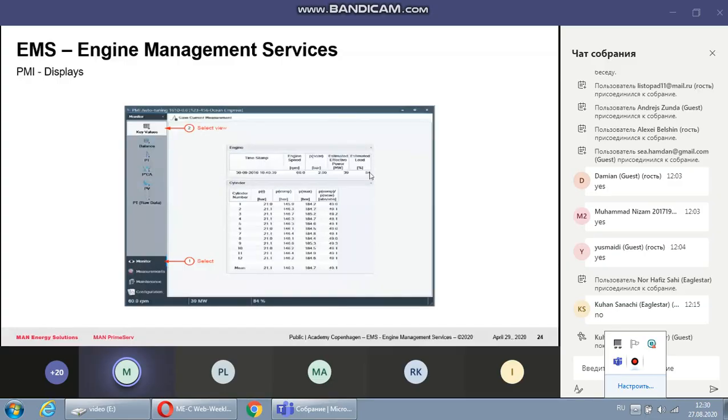So you took +5. Then waited for some time, 20-30 minutes, and you found the difference is 75 to 84. So now you go manually to the FQS, click, and then with the arrow mark showing downward or upward, push and see whether 75 becomes 80 or 75 goes to 72. So if you are not sure which direction you need to go, just increase by 2 or decrease by 2 and watch what happens. Then if it is in the right direction, you are right. Otherwise, change the direction. Very simple. Nothing more to do. So that's how you need to adjust. We are going to do that in a minute.